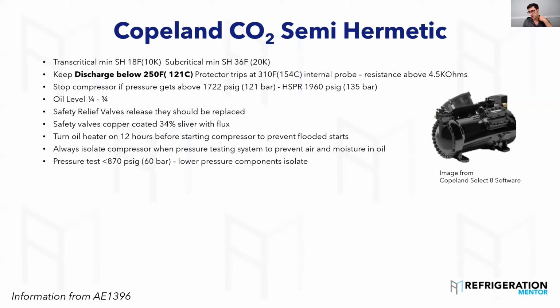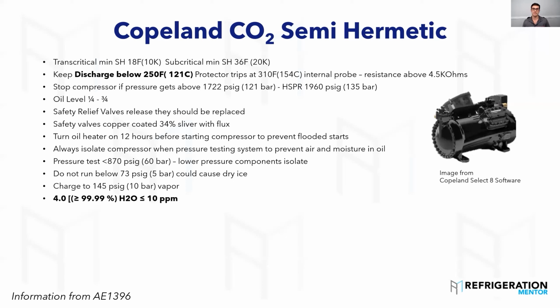Pressure test below 870, 60 bar. Always want to remove any component that doesn't meet that. For an example, if you're doing on the subcritical side, some of those components may only be up to 680 psi, or I think it's 45 bar. I'll have to double check that. But you want to make sure you pull those ones out if you're pressure testing higher than that. Do not run below 73 psi or 5 bar. That's below your triple point. Charge of 145, 10 bar.